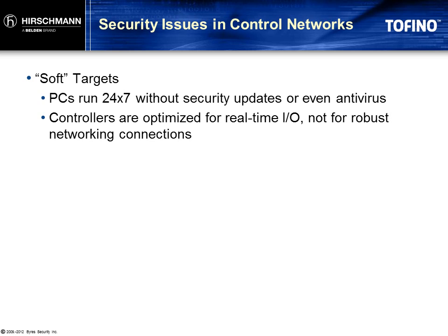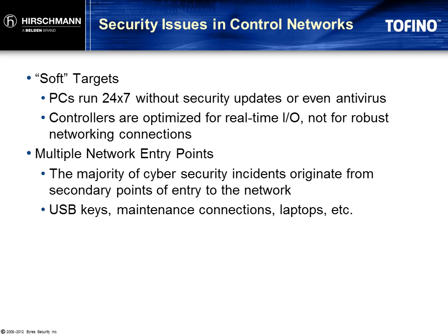Second, many control networks have multiple pathways through which cybersecurity threats can enter the plant. These pathways often bypass existing security measures and some of them don't even appear on a network diagram. For example, laptop computers that are carried in and out of plants, or USB keys that can move from one PC to another, can easily bring malware into the plant and rapidly spread it from one system to another.